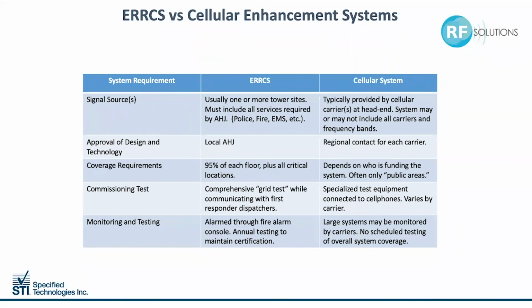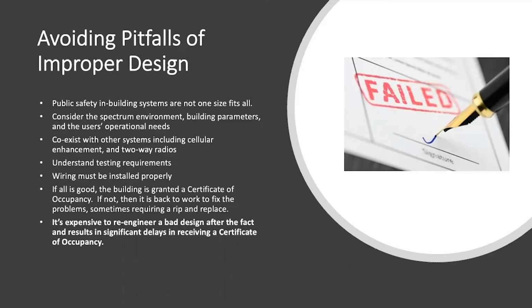Monitoring and testing of cellular systems is again dependent on the various carriers involved, as well as the size of the system. ERRCS must adhere to published standards for regular monitoring and testing. Public safety in-building systems are not one size fits all. Each design has unique requirements, some of which are defined by the AHJ, and many of which vary with each individual building. There can be several other wireless systems in a building, and poor design of any one of those systems may result in interference with first responder communications.